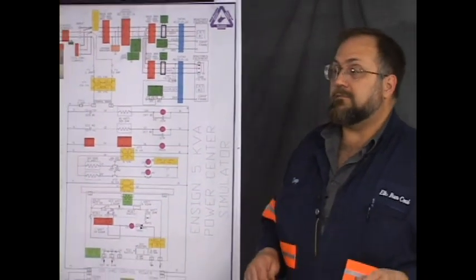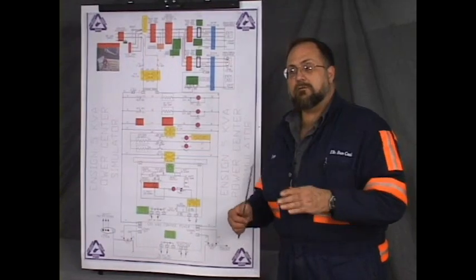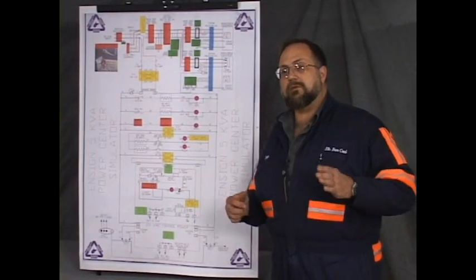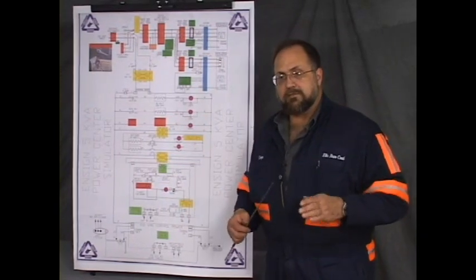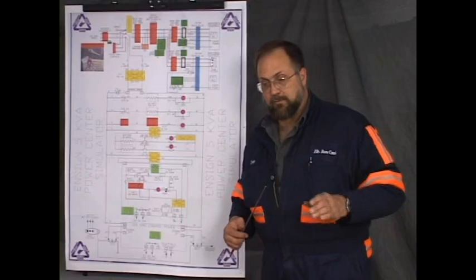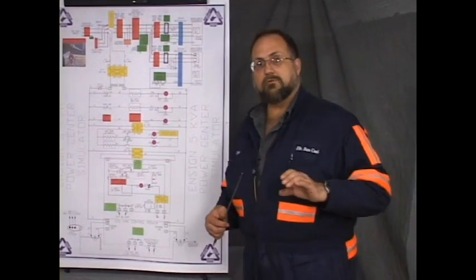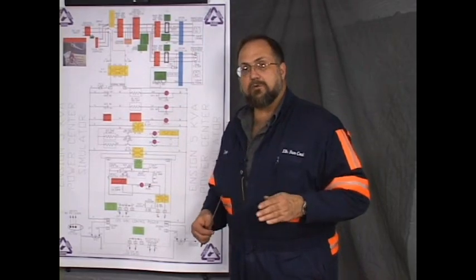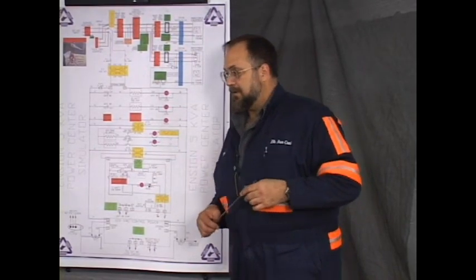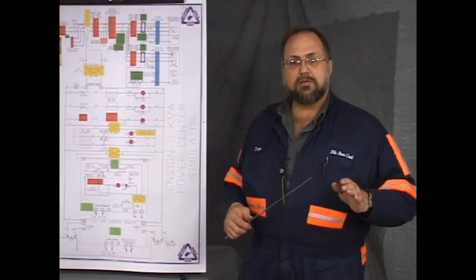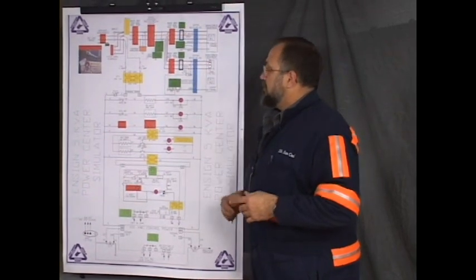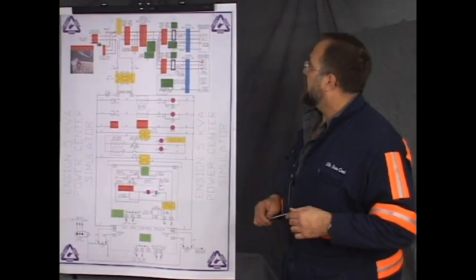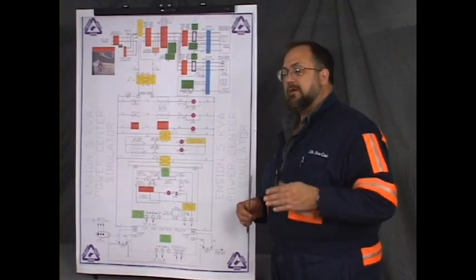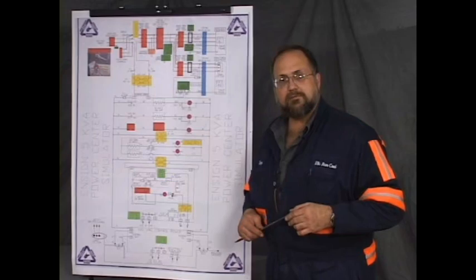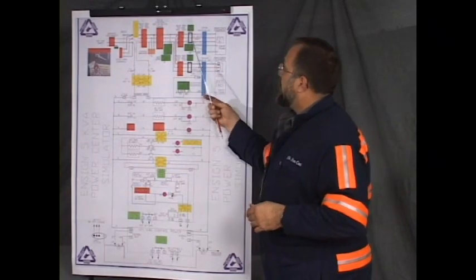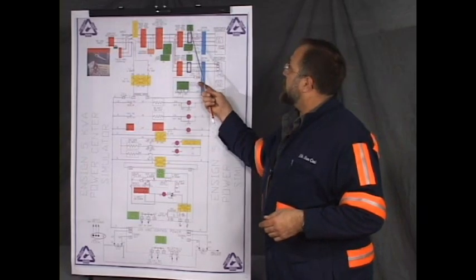Now, with 3 phases involved, they're offset 120 electrical degrees. And so while one phase is ascending, there's always a corresponding phase that is descending, so the magnetic flux stays at a comparatively constant level. While one of them is building, another one is falling, and the net result is a small change or no change in the field. Should one of them become grounded, that changes the flux. That will either provide a gap or a constant that's not matched by another phase. And the flux field that's left is enough to induce and drive the relay.